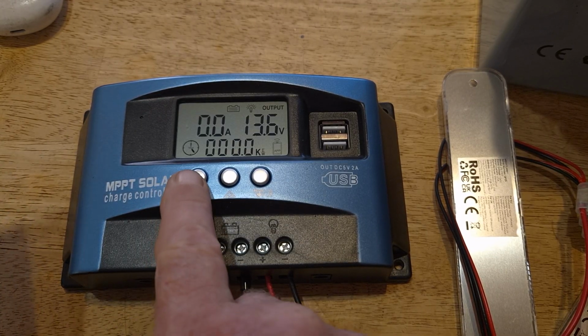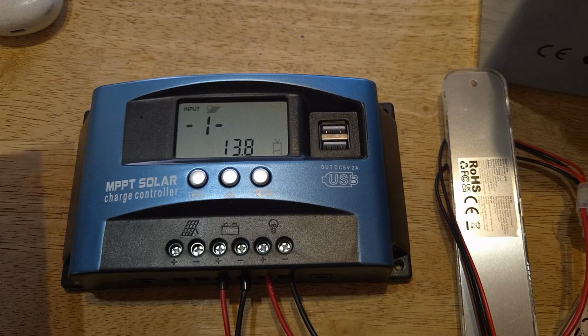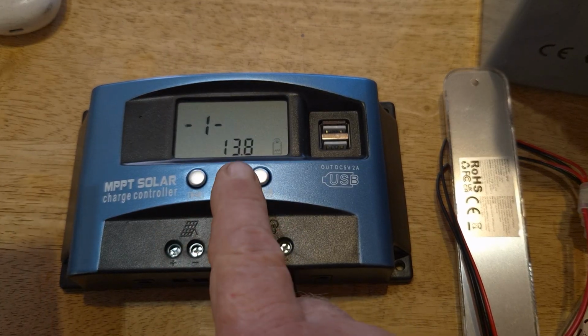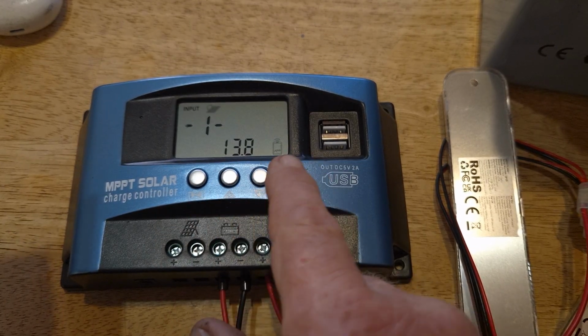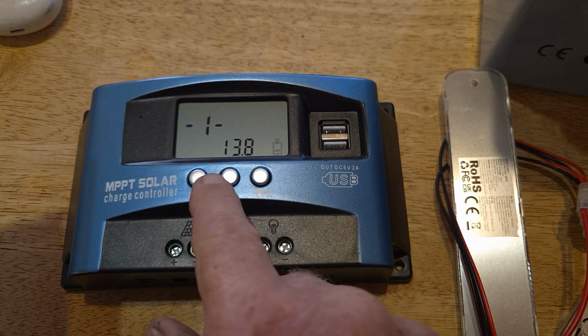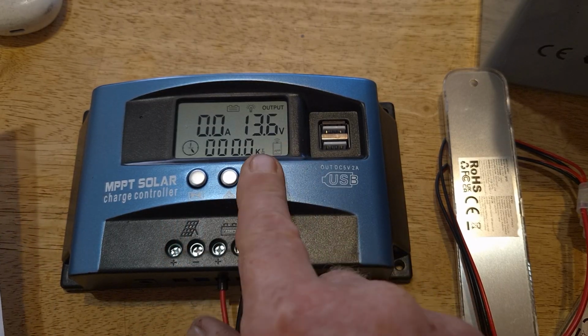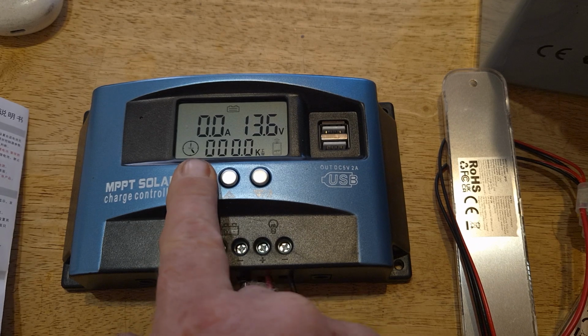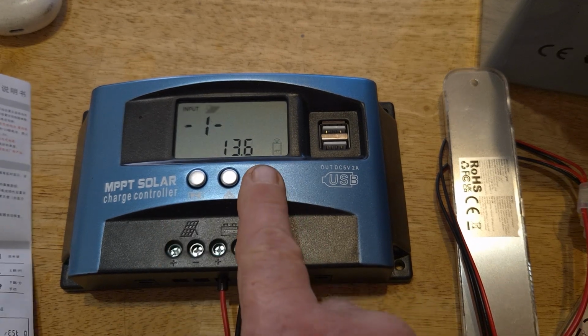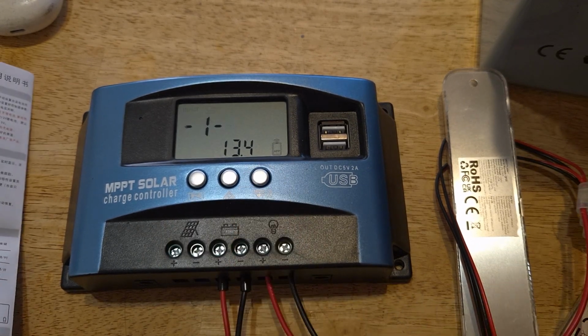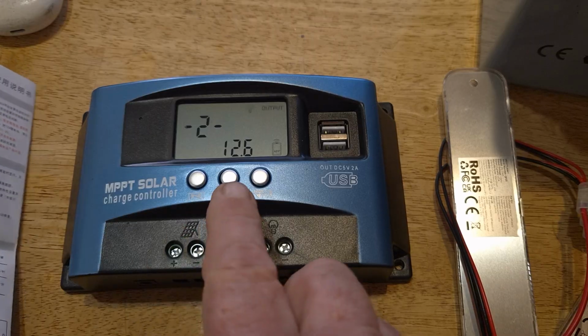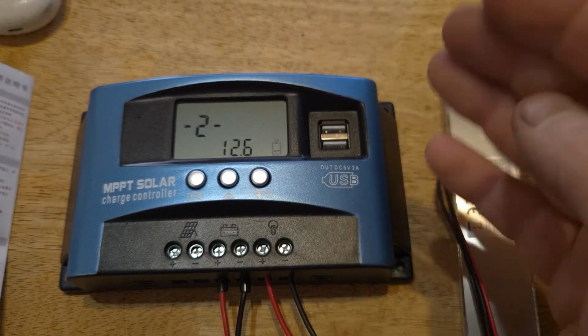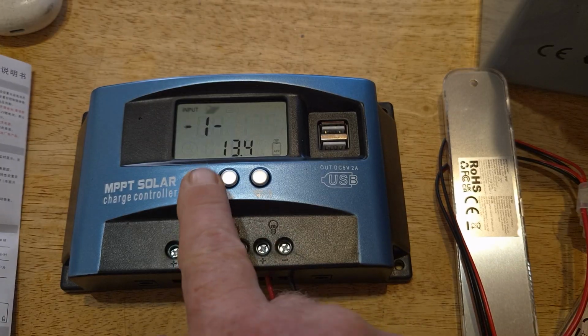So let's run through them quickly. To get into your settings, you press 1. That's your float charge, which I'm going to leave at 13.8, because that's kind of what it can go down to, you see how it goes out, being a lithium, 13.4. Then you press that again, and we get to the discharge recovery, which is 12.6.